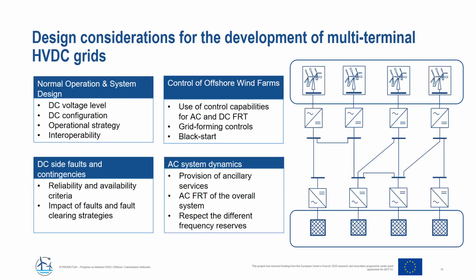The fourth part that has to be taken into account is the AC system dynamics. With the DC systems becoming larger and larger, it will be more important for them to provide auxiliary services to the AC system, and also vice versa. And the overall AC fault ride-through of the system has to be ensured, and also when connecting those larger DC systems to different synchronous zones, it has to be ensured that the different frequency reserves are respected or accordingly changed. So overall, there's a broad range of possibilities to design those DC grids, with different control features, different configurations, specifications, and criteria. And there's not yet a standardized DC system.